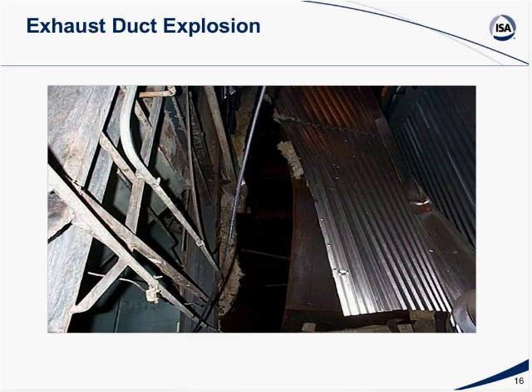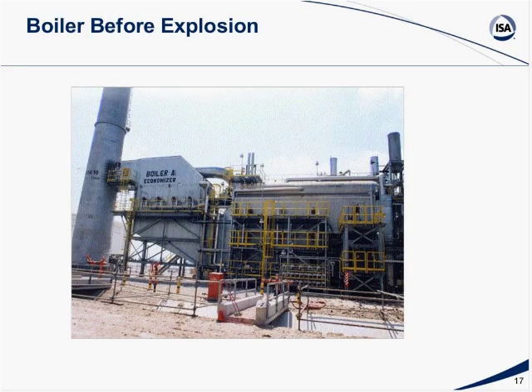This next one is a case where the fuel mixture got rich. It was in the duct work. When they tried to light off, they got the fuel going in before the air came in. When the fuel started coming in and then the igniter came on, they had an explosion. So they had a fuel-rich mixture in the duct work. That's what this picture covers, that explosion in the duct work. This is a real bad but good example of operators not doing what they were trained to do, or trying to bypass the system.